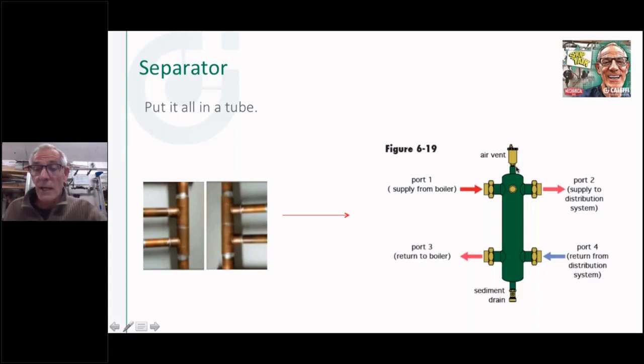And by the way, couldn't we put an air vent on top of this? Because this is going to be a low velocity zone, this big wide spot in the road, let's call it. It's going to turn into a low velocity zone. Great place for air to rise up and grab air. And couldn't we also catch some sediment at the bottom as the particles from a rusty old system come in here with low velocity going through them, they could drop to the bottom. So now I've taken my hydraulic separation and kind of enhanced it, turned it into air separation, turned it into a bit of a dirt removal function also.